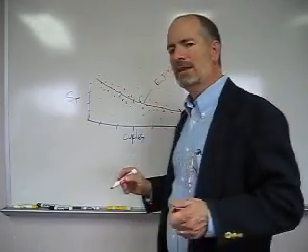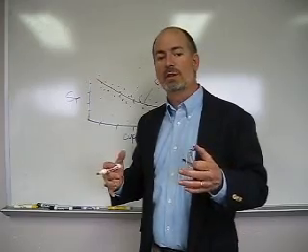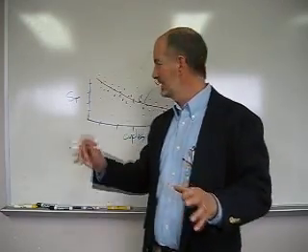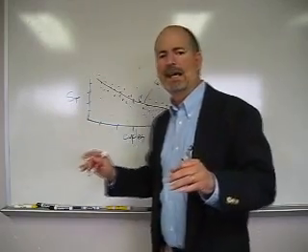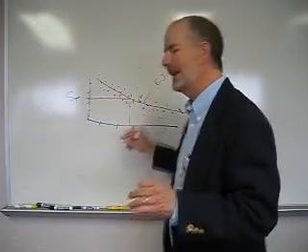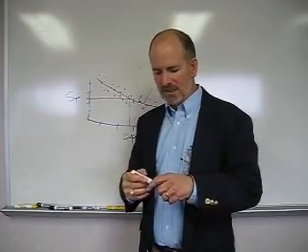So now, if you're going to do a bellows design, you don't need to go cycle test that particular design. All you need to do is run the calculations based on those same equations that come up with this total stress range, and then you go down your curve, and you find your point, and that's your calculated cycle life for that bellows.